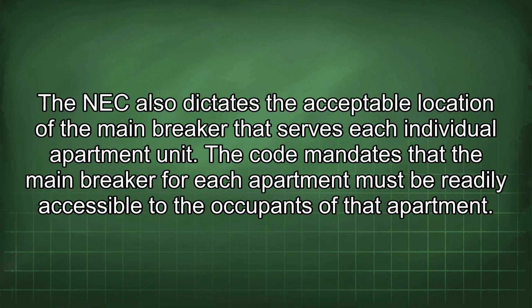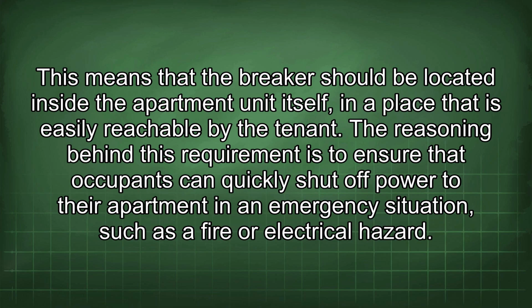The NEC also dictates the acceptable location of the main breaker that serves each individual apartment unit. The code mandates that the main breaker for each apartment must be readily accessible to the occupants of that apartment. This means that the breaker should be located inside the apartment unit itself, in a place that is easily reachable by the tenant. The reasoning behind this requirement is to ensure that occupants can quickly shut off power to their apartment in an emergency situation such as a fire or electrical hazard.